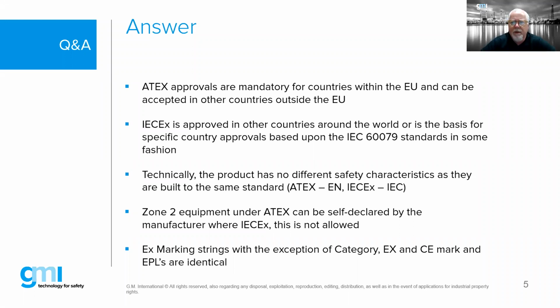The standards themselves, under the ATEX directive, which is the requirements within Europe, you have to follow what are called EN standards. In the international world, you have to follow the IEC standards. The IEC standards and the EN standards are basically one and the same. The only differences are in the annexes that you will find within the EN versions, which reference other EN standards and certain stuff like that. But technically, they're the same. Zone 2 equipment under ATEX can be self-declared by the manufacturer. Under IECEx, this is not allowed.